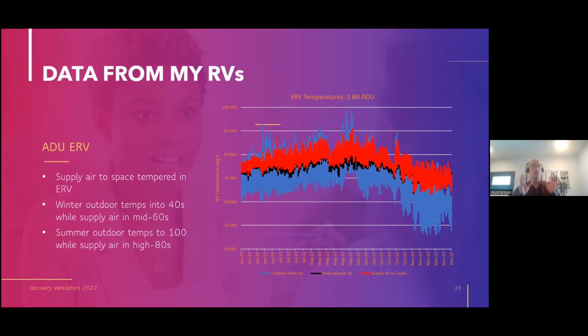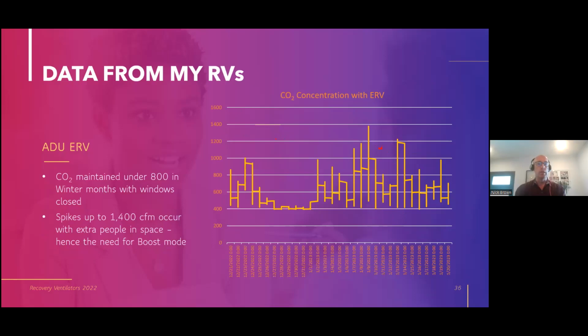Because the fans, and there's 2 fans in that box, are not 100% efficient at moving air. They create some heat. So ERVs are tempering the indoor air, but also adding some heat to the airstream. And I've come to believe that that's why they perform a little better in heating season than cooling season, and thus they perform better in climate zones with more heating demand than cooling demand. And you'll see that our modeling data lines up with that. But you can also see with these red lines, really nice tempering actual data. Yeah. I thought that was pretty cool. First time I ever looked at that.